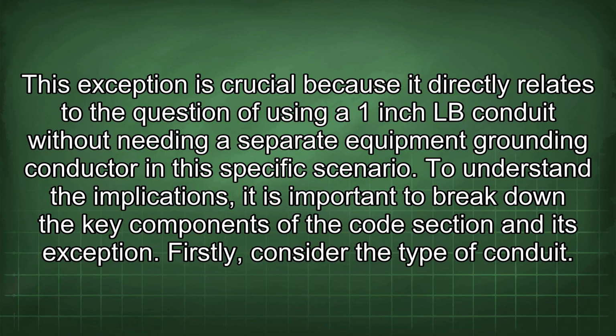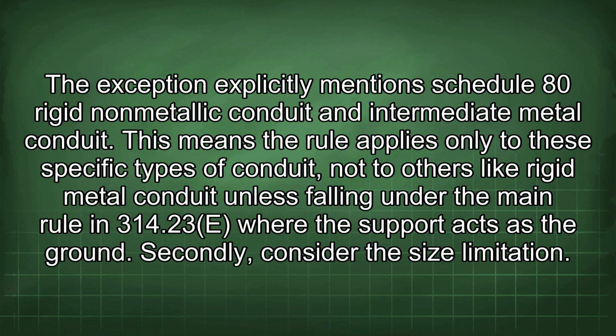To understand the implications, it is important to break down the key components of the code section and its exception. Firstly, consider the type of conduit. The exception explicitly mentions Schedule 80 rigid non-metallic conduit and intermediate metal conduit. This means the rule applies only to these specific types of conduit, not to others like rigid metal conduit, unless falling under the main rule in 314.23(E) where the support acts as the ground.